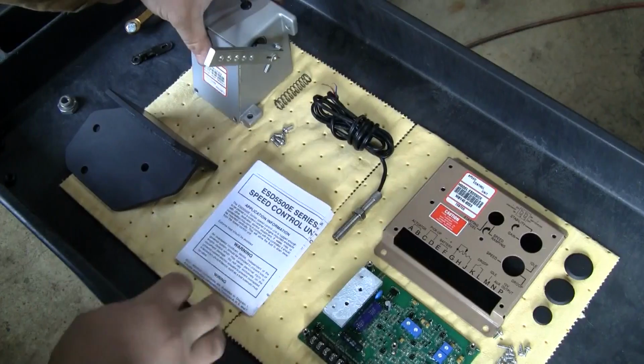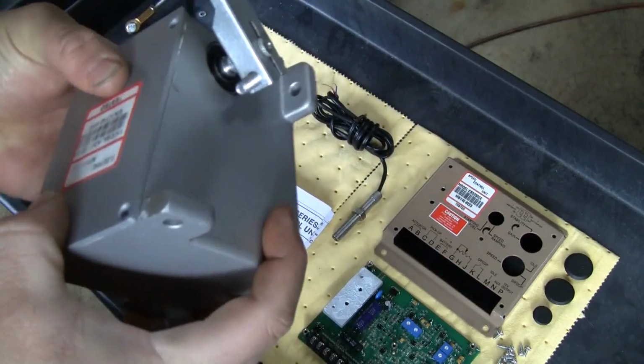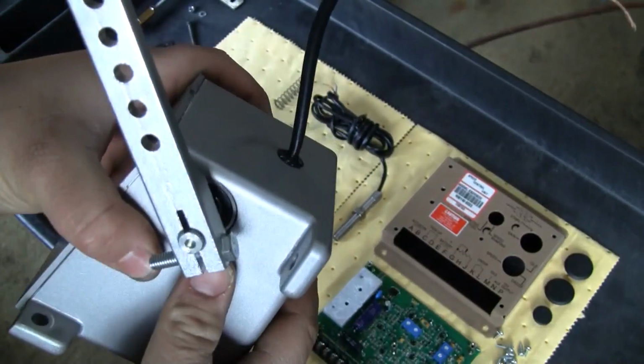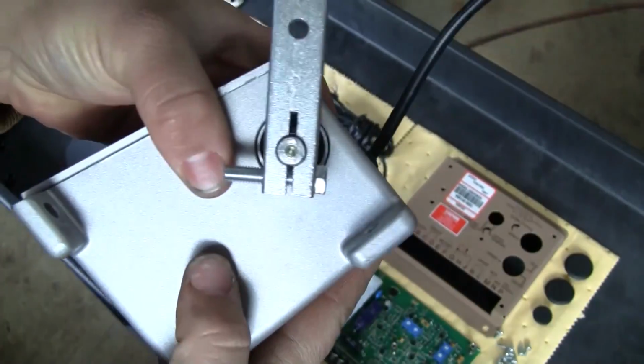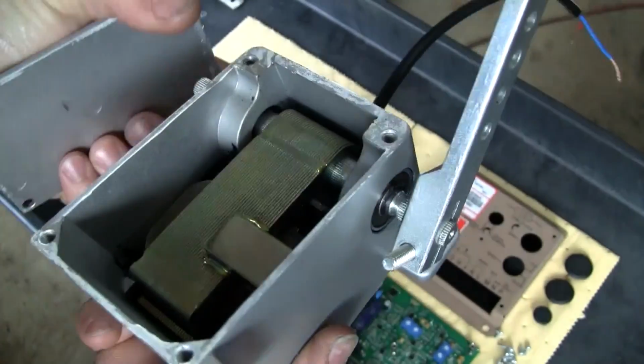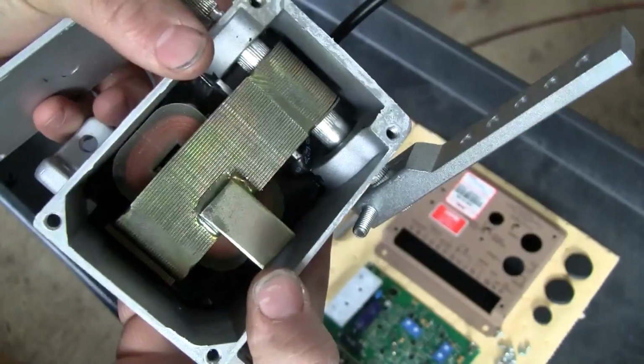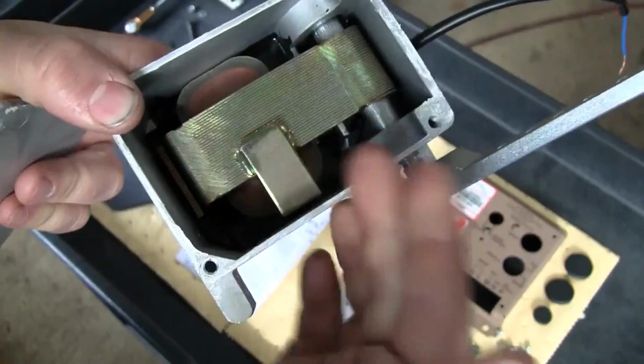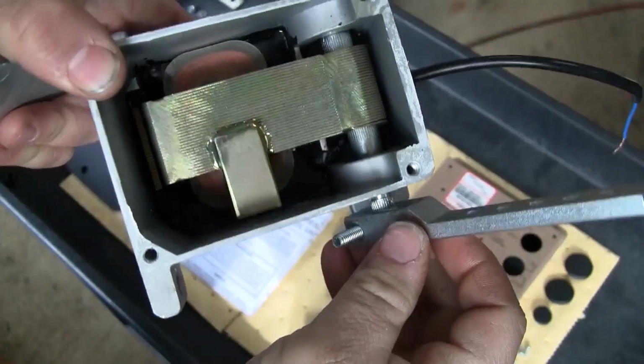Here's the actuator, let's look at the actuator. It's a cast aluminum body, got ball bearings on the actuator shaft. I took the screws off the front cover here so you can see - this is what an electronic governor actuator looks like on the inside.